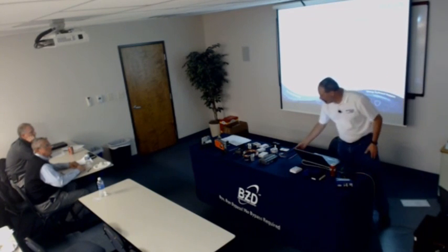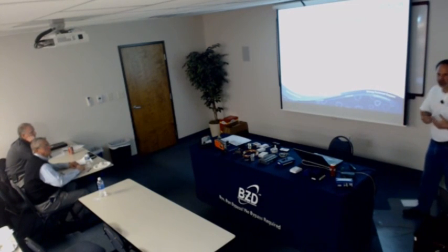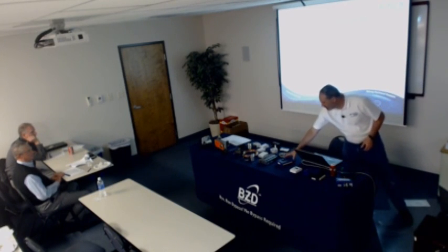So whether you decide to have a LonWorks system or a BACnet system might depend on a couple of things. Personally, I've been doing Lon for the 13 years I've been here, and probably 5 years before that at Trane we were doing Lon-based controllers. That's the one I like the best. I've been doing it the longest, and it has some real advantages. When you put together the communication bus on a Lon controller and the wire runs from unit to unit, it's not polarity sensitive. It doesn't care. If the electrician installs it, screws it up 4 times, you're not even going to know. It'll just keep on running. If you do that with BACnet, somebody's going to spend a lot of time in the ceiling checking all the terminations.